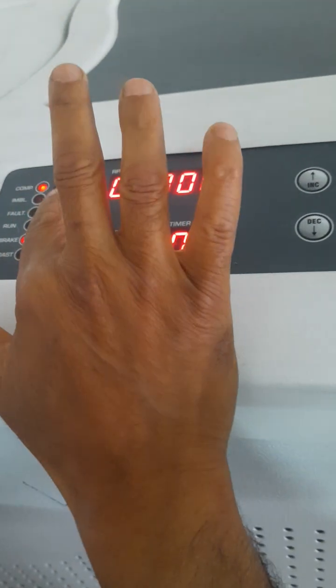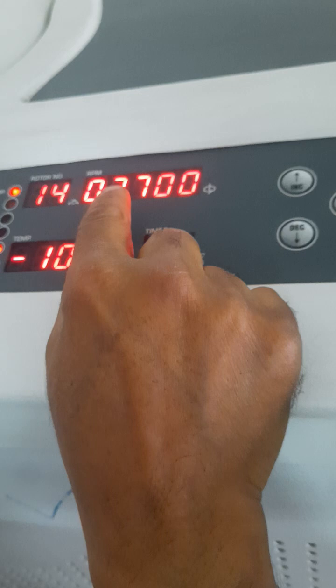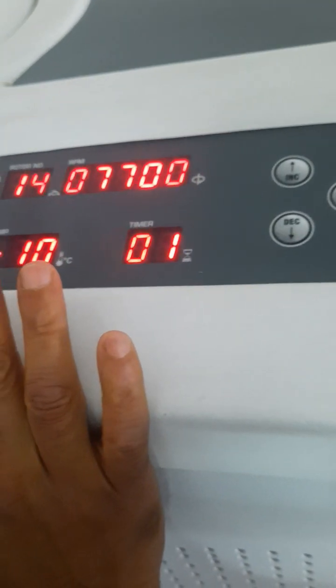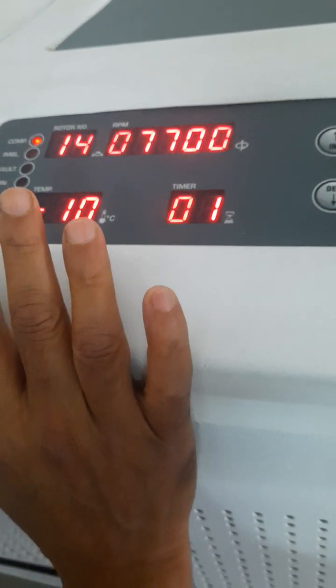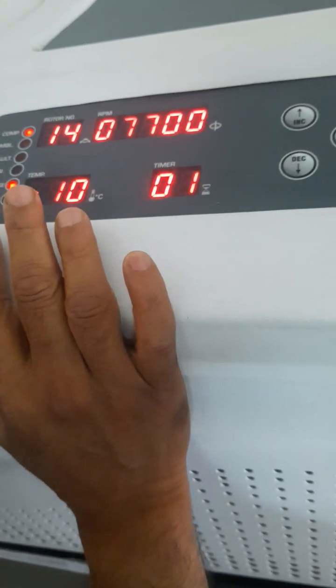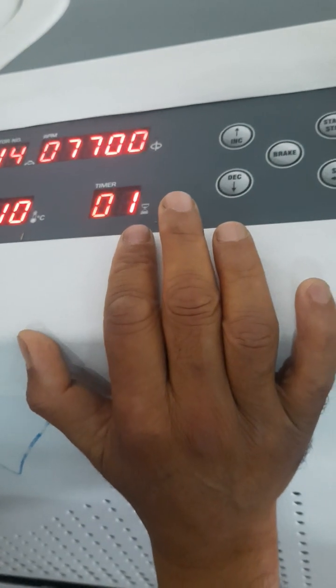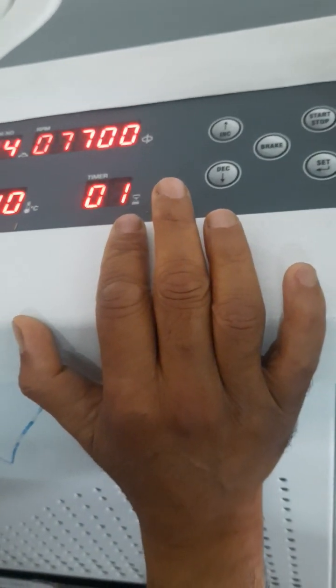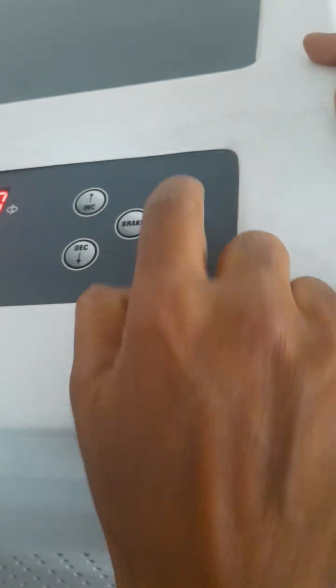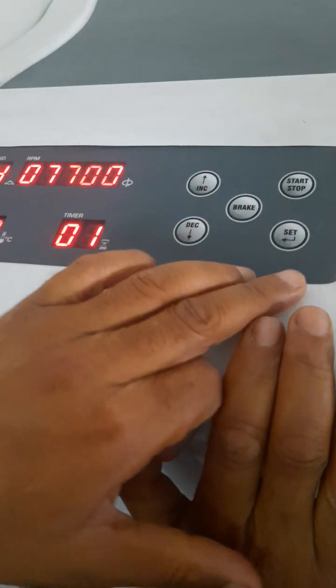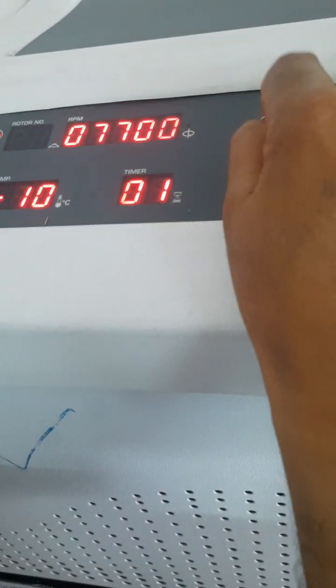Here on this display we will set the different components. For example, we will set the rotor number. Rotor number is already set. We will set the rotations per minute. That will vary upon the sample, and we will set the temperature. If it is analysis of DNA, analysis of RNA, blood sample, we will accordingly set the temperature. And this is the timer for what time we require this centrifuge to operate. So I will go to this set button. I will set first the rotor number. Rotor number is already set. This is rotor number 14.